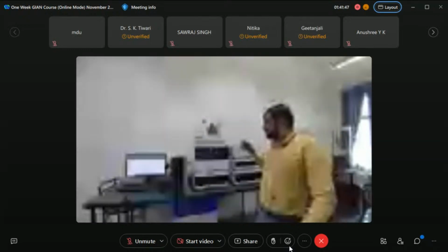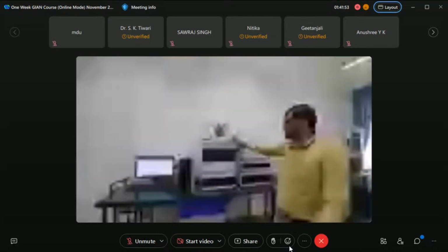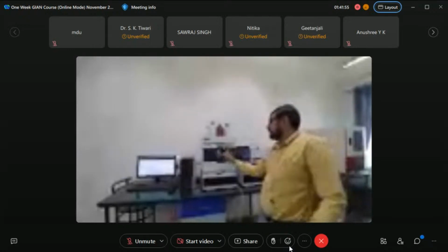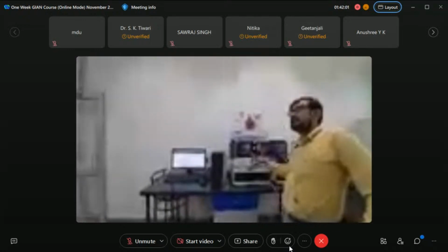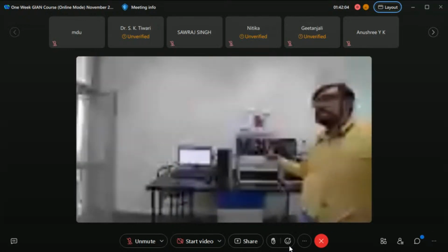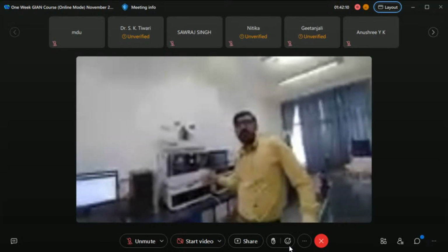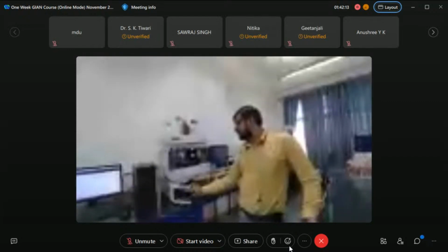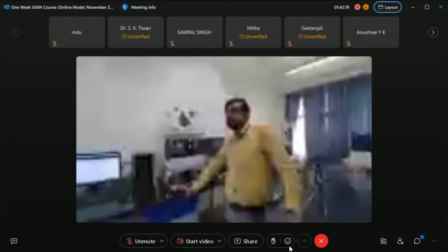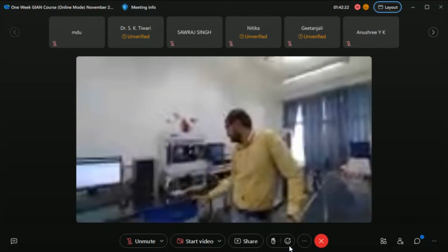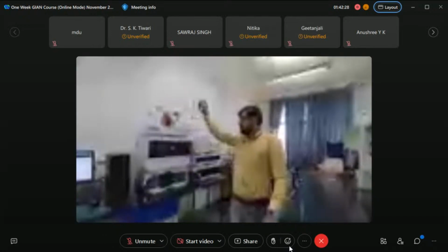In this system, we have the quaternary system of the HPLC, in which here is the robotic head of the system, which takes the sample from the sample tray and puts it into the injection port, and the injection inserts the sample into the injecting loop. Here the mobile phase comes through various pumps. There are majorly four pumps, so our system is a quaternary system. The pump supplies the mobile phase to the column.